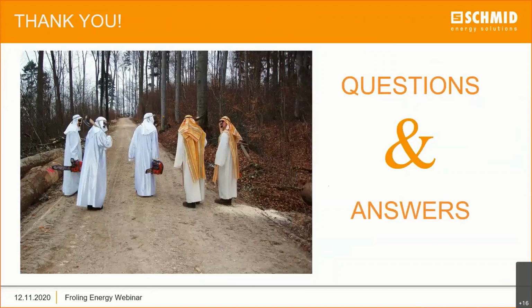And in this case, we brought the boilers over. We've got a half a dozen installations at this time, mostly burning the dry wood chips. In fact, all of them, I think, but maybe one has a little bit of a wetter chip involved, but most of them have the dry wood chips. And what we've discovered is that we pass our requirements with flying colors without using an ESP, which has been quite good when it comes to return on investment, because they can easily be $250,000 and up to install one of those. And in the end, it ends up being a much more cost-effective installation.